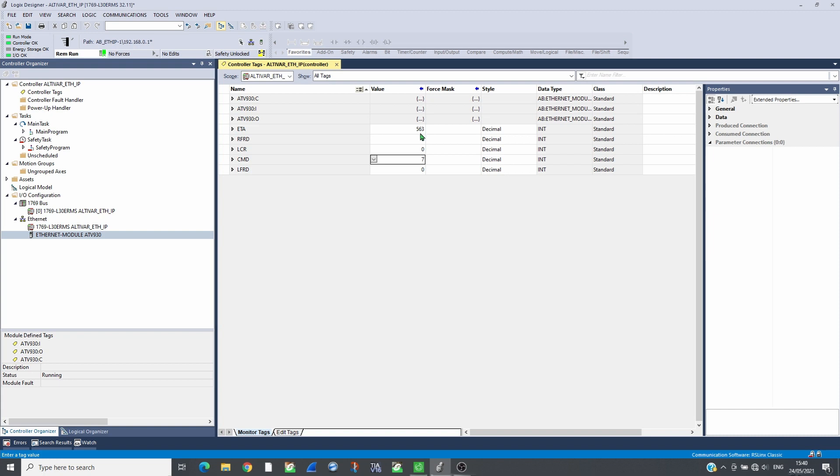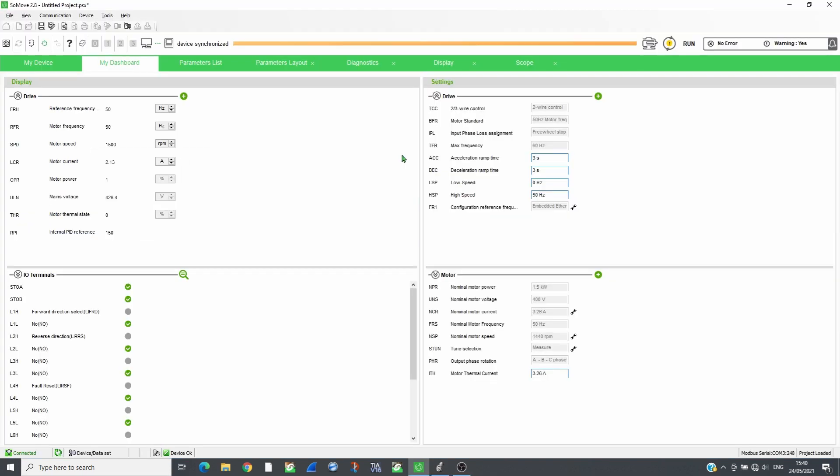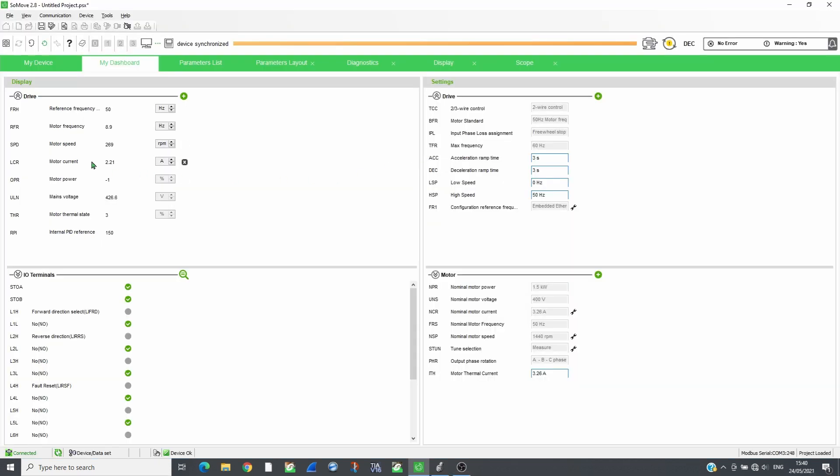Send the reference in LFRD, 1500 RPM. Send 15 in command to run the drive. RFRD will show the motor speed and LCR will show the motor current. These values match those shown by SoMove.